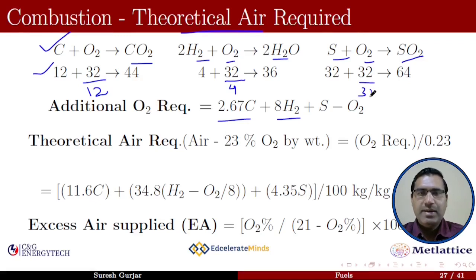Similarly, the oxygen required for S percentage of sulfur is 32 divided by 32 multiplied by S percentage, which equals S. Since we already have O2 percentage of oxygen in the fuel, that percentage has to be subtracted. So the additional oxygen requirement is 2.67C + 8H2 + S - O2.